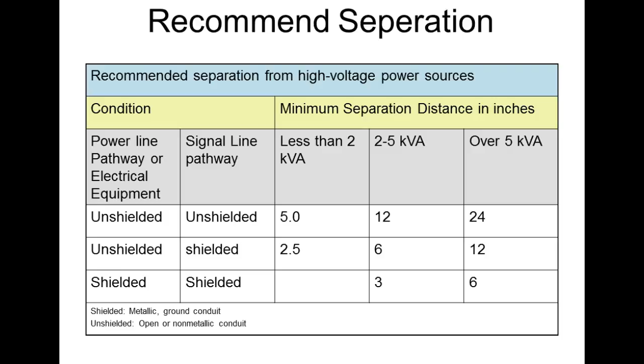It gets crossed. So sometimes you cannot avoid crossing a signal cable with a power cable, but if you ever do it, you need to cross it at 90 degrees. Does that make sense? And also, you never want to run those things side by side or put them in the same conduit.